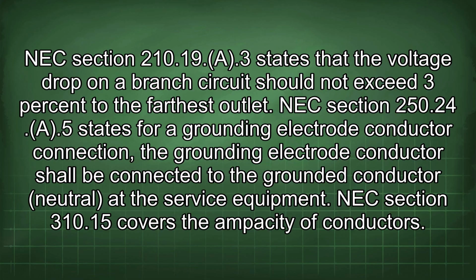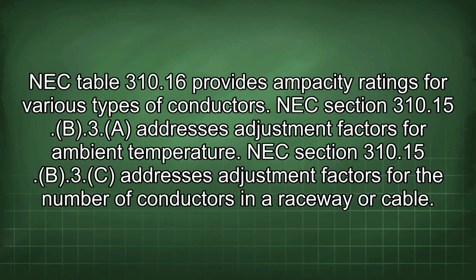NEC Section 250.24(A)(5) states for a grounding electrode conductor connection, the grounding electrode conductor shall be connected to the grounded conductor (neutral) at the service equipment. NEC Section 310.15 covers the ampacity of conductors. NEC Table 310.16 provides ampacity ratings for various types of conductors. NEC Section 310.15(B)(3)(a) addresses adjustment factors for ambient temperature. NEC Section 310.15(B)(3)(c) addresses adjustment factors for the number of conductors in a raceway or cable.